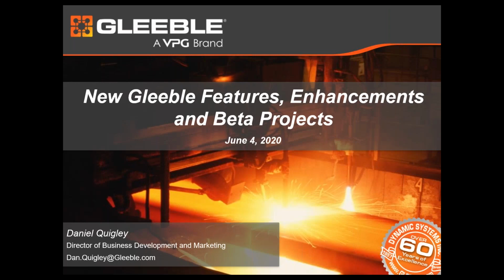I've noticed a few questions on the question board, and I think most of them have been answered in general, but it may be useful to expand on a few of them. There were a couple of questions about what is available with the induction heating. As Dan mentioned, we have introduced a new induction heating system for the Gleeble. As you all know, the Gleeble typically has used direct resistance heating to directly heat the sample, and that is very beneficial for a number of reasons because it heats the sample very quickly, it heats the surface and the center at the same rate, and it can generate high thermal gradients in the sample to simulate things like heat affected zones. But there are times when you may want a very low thermal gradient, and there are some experiments where you may want to actually just simulate the results of induction heating. So we have added this.